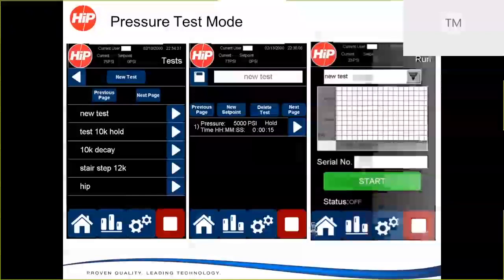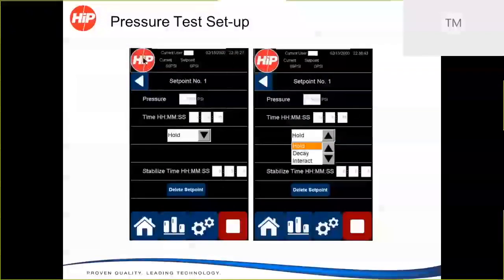The next screen will show some of the details there. In this case, the example is for 5,000 psi, but this is a hold test. So it's saying let's run to 5,000 psi. The time that we want to run that for is 15 seconds, and we want to hold pressure. Hold pressure means that we're going to keep air pressure on the pump. So when we run that pump up, we are going to very precisely maintain exactly 5,000 psi on that test. We also have two other options for how you can run a test. The next one is decay.